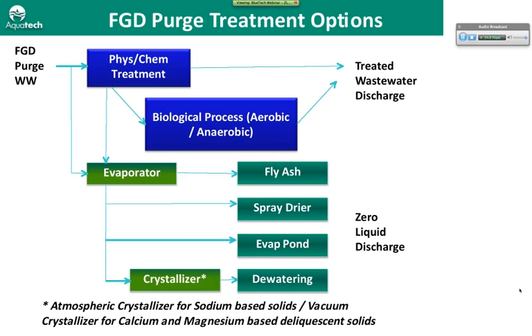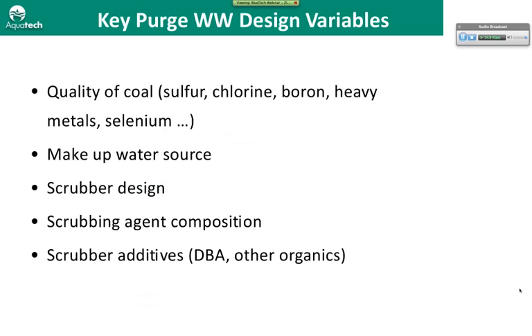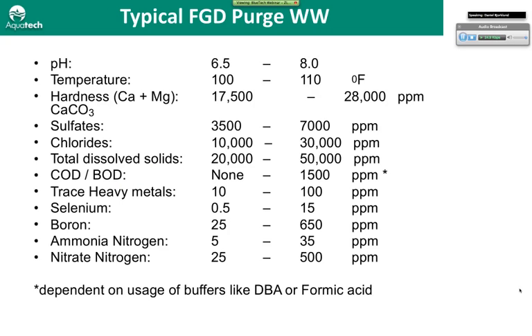As we look at FGD purge treatment, there are a number of options. Traditionally, FGD blowdown has been treated by biological processes and then discharged. And where discharge is not available, then ZLD processes come into play, where we utilize an evaporator, and we can either take blowdown directly and mix it with fly ash in some instances. There could be a spray dryer to achieve ZLD, an evaporation pond, or the system goes full ZLD with the addition of a crystallizer and dewatering equipment. Typical FGD purge wastewater chemistry is characterized by very high sulfates, hardness, chlorides, and TDS.